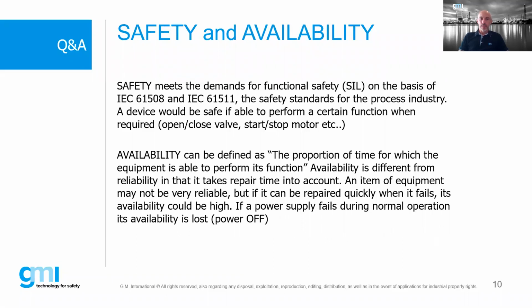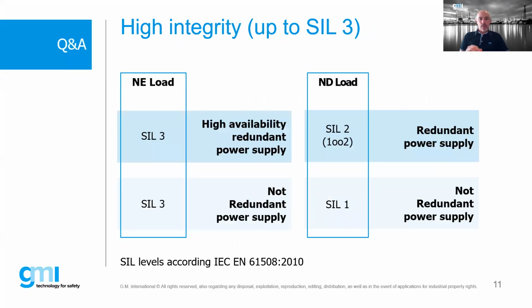Besides the safety, availability is a factor that is really required, because one day where your plant is stopped can cause maybe a million euros or dollars in losses. And this is a configuration we already showed you, but I want to repeat: remember that for a non-energized load, if you are using safety power supplies, SIL3 is already reached by using just one power supply, non-redundant. So you reach the safety, but you don't reach the availability. It means that HFT was the question from one attendee before.